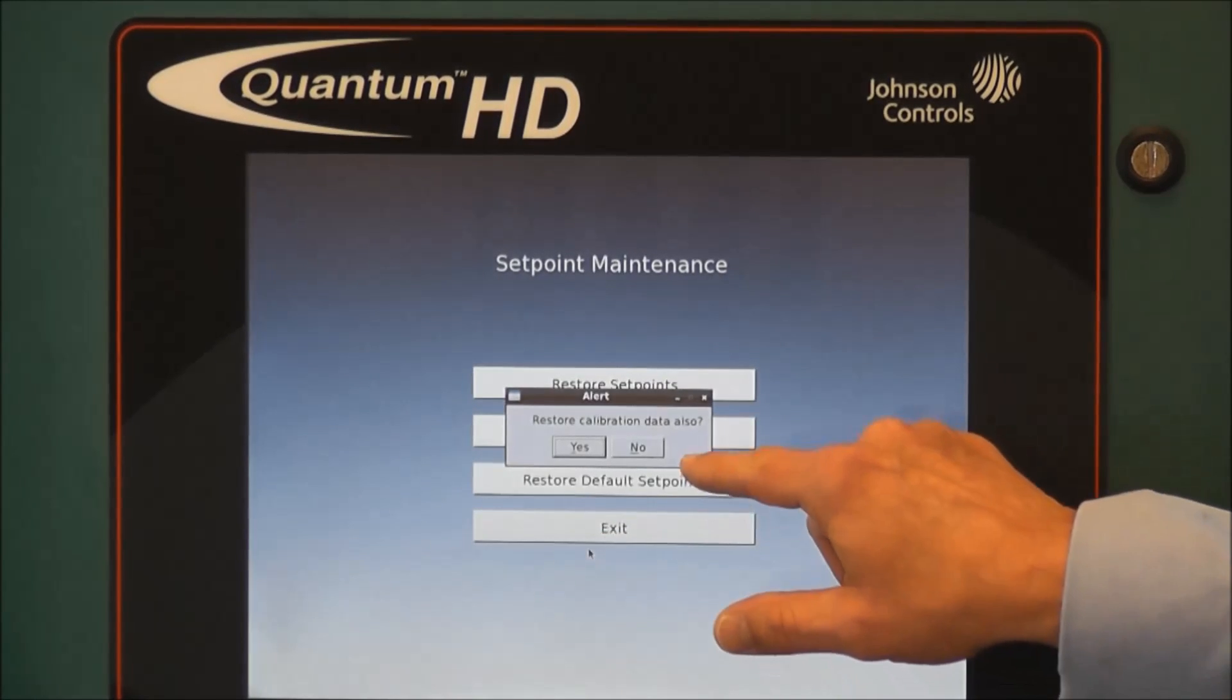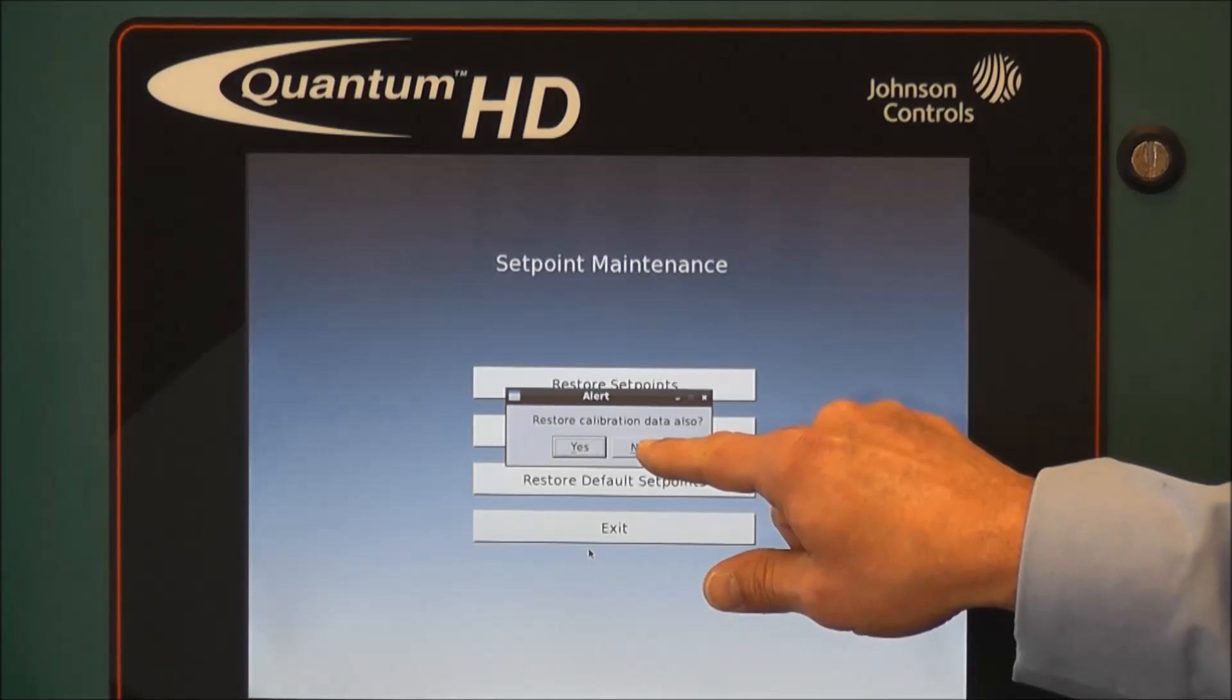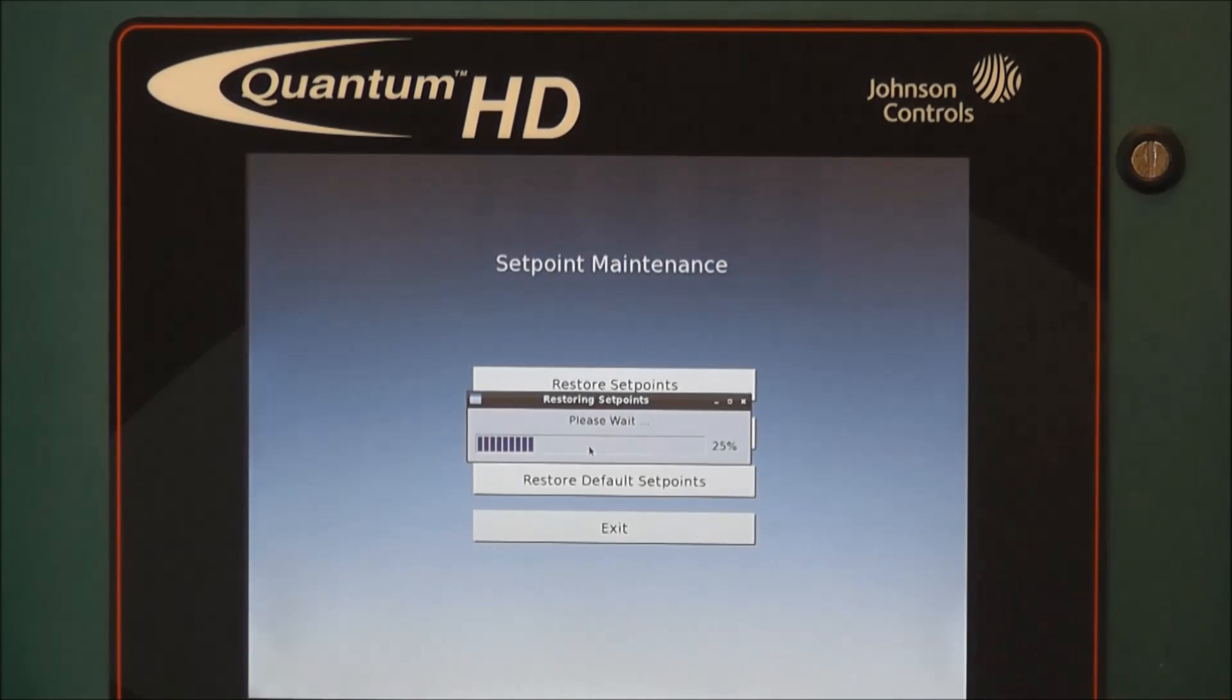It's going to ask if you want to restore calibration data as well. And in most cases, you will. However, if you are restoring or transferring setpoints from one controller to another, you may not want to restore the calibration data.